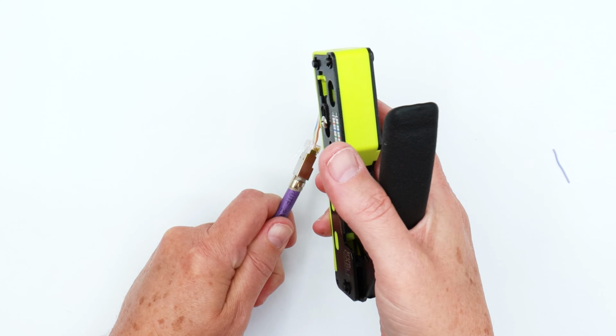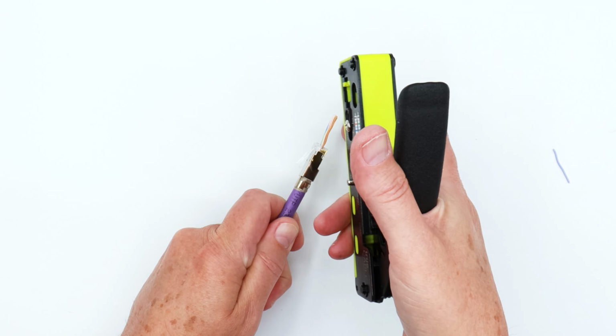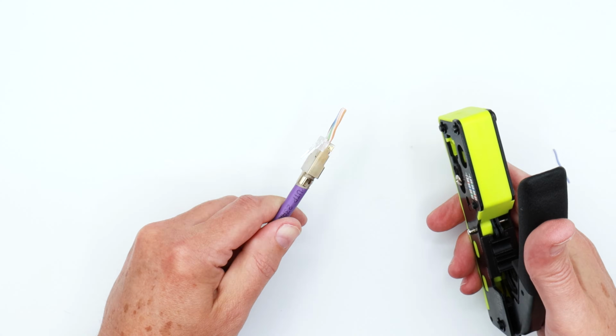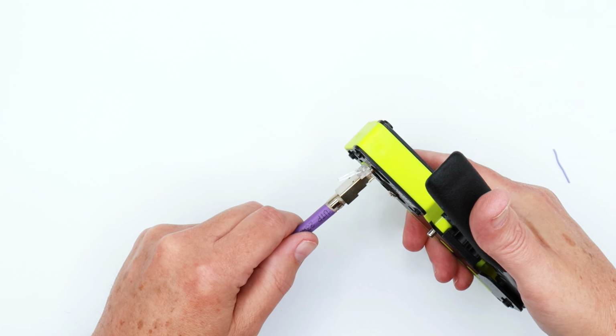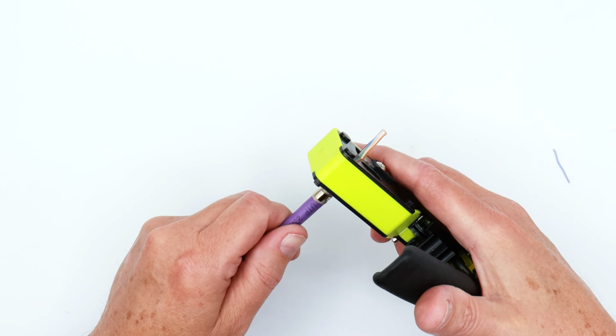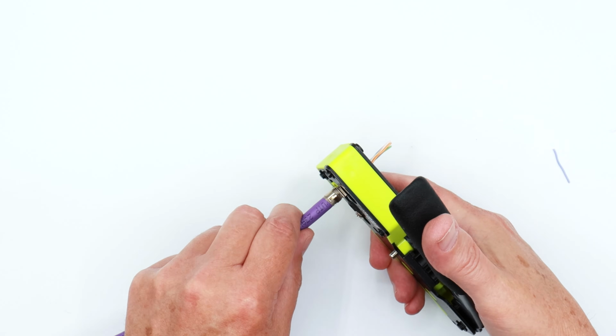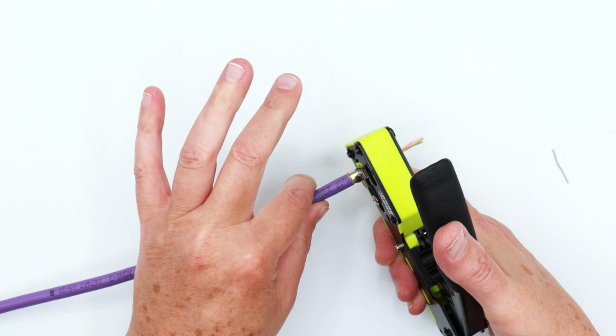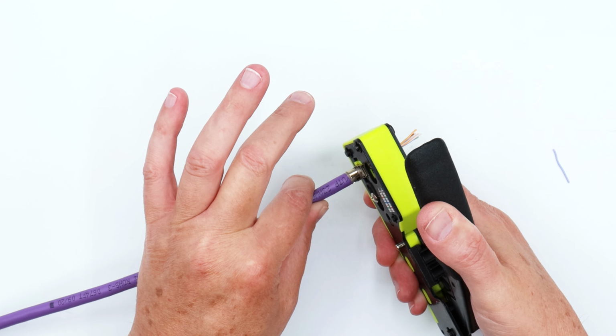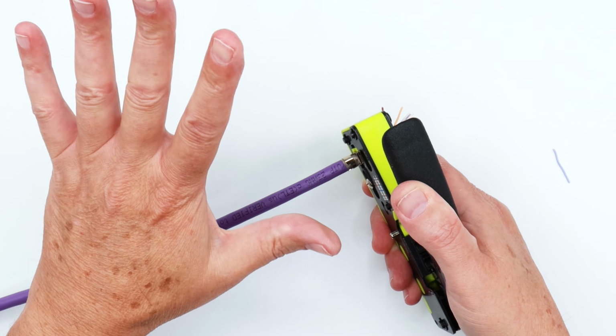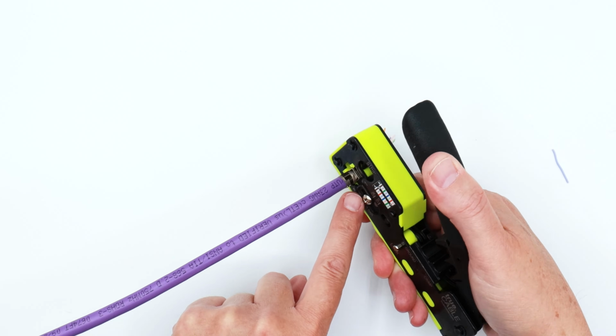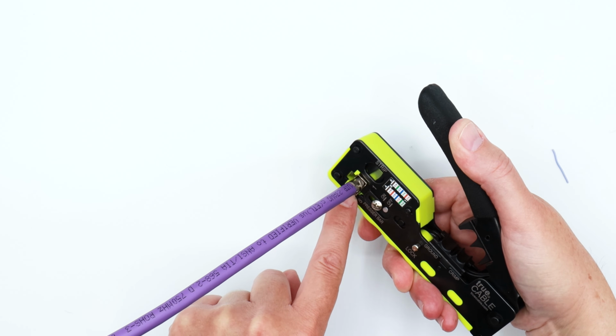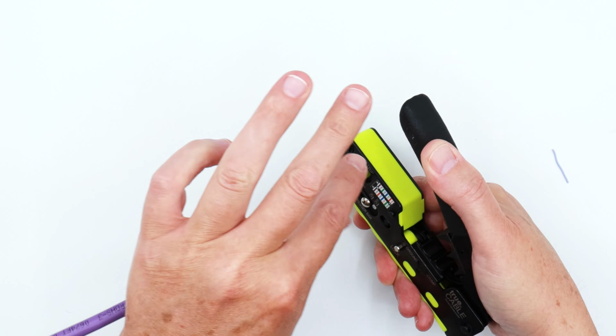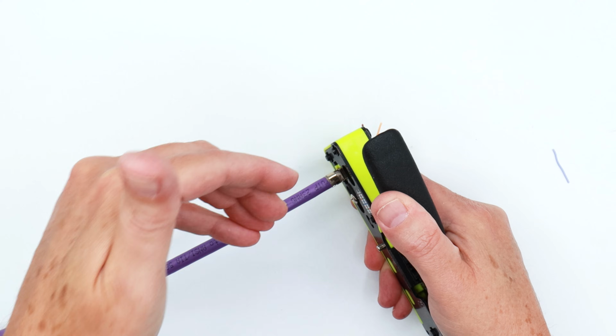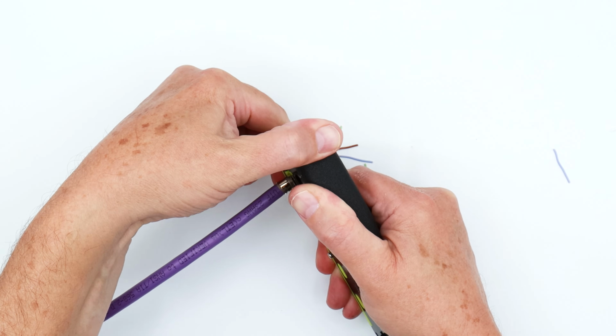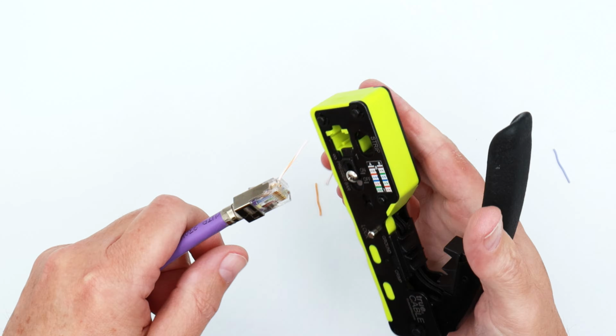Ramp up your conductors at a very mild angle, not a severe angle, maybe 5 degrees at most. Put it into the tool. Make sure all those conductors clear that flush cut blade. Now push it until it's fully seated. As you start to close it, take your hand off, just like that, because that strain latch pressure bar going into the rear of that housing is going to reposition the plug for you for a proper termination. And then all the way down, let it up.